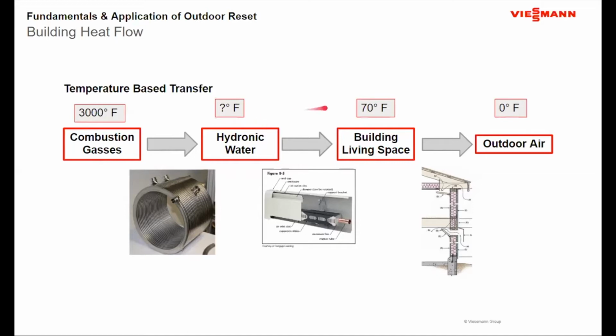That water temperature is tied to how comfortable the building is going to be, but also from an aspect of performance, when I start to look at and select the water temperature, that water temperature affects the heat transfer in the heat exchanger of the boiler. So the water temperature also plays into how efficient we can be in taking that heat that's being generated in the combustion process and extracting it into the water to heat the building.